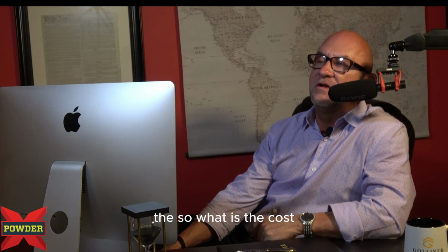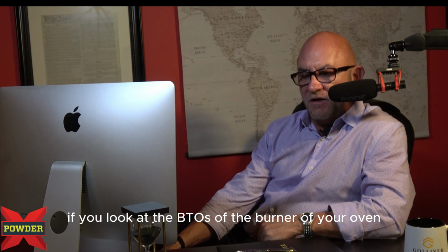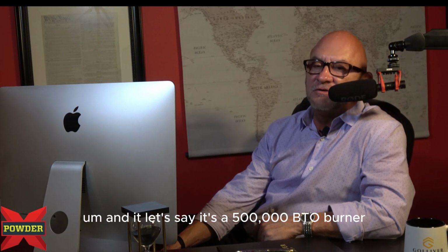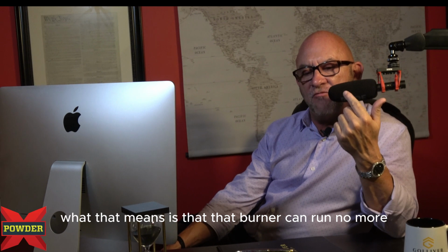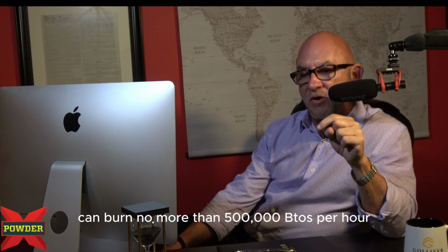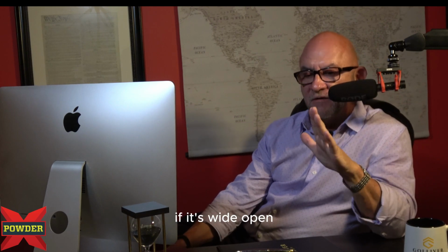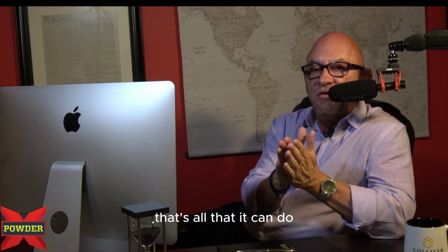So what is the cost? Basically, look at the BTUs of the burner of your oven, and let's say it's a 500,000 BTU burner. What that means is that burner can burn no more than 500,000 BTUs per hour. That's the max. If you think about it like a car, if it's on the floorboard, that's all it can do.